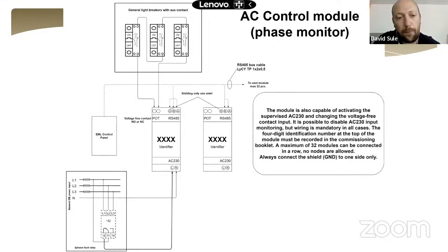This schematic diagram shows this AC control unit's options. Firstly, we have to give AC230 to this module. The best way to monitor the general light sub-dB: first we have to monitor the three incoming phases of the dB. First, we have to use a three-phase fault relay. This is at the bottom of the picture, this three-phase fault relay. And from this relay output, we have to give one phase and neutral to supply our AC control module. At the top of the picture, we can see the general light breakers, which are installed in a sub-dB. These breakers have a physical position. It can be on and off.